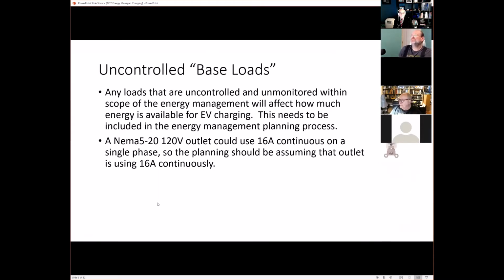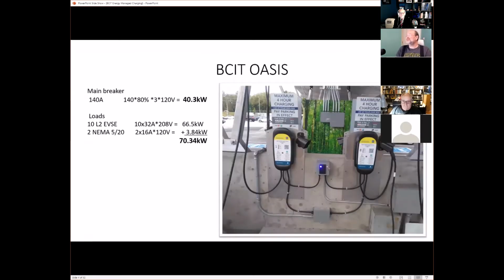So then we get into what we actually came to talk about, which is having an energy managed system for a building. At BCIT Oasis, we had enough power for about 5 charging stations, a little over 5. We had a breaker panel with a 140 amp main breaker, which through the calculations I've shown is only about 40 kilowatts of charging for level 2.